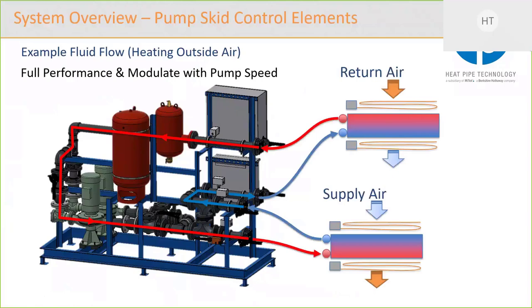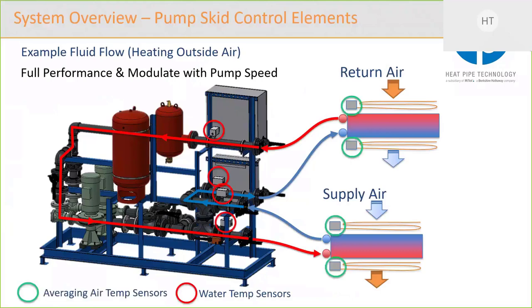So this is how the coils are connected up to the skid. Here you can see that there's two coils, and it shows the temperature sensors upstream and downstream of the coils. Just take a moment to show you that the water temperatures are being measured on the skid. And as I said, the only sensors that are not on the skid are the air temperature sensors, and you can see those in the green. Those are what would have to be wired to the controls. Everything else is already pre-wired on the skid in the factory.